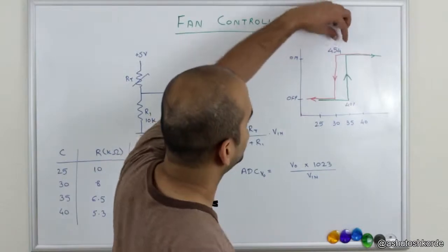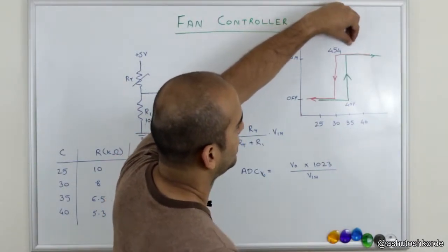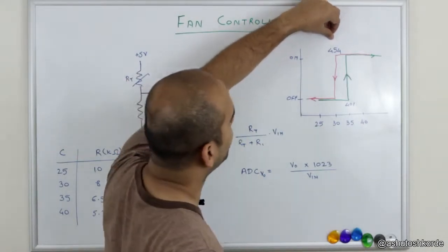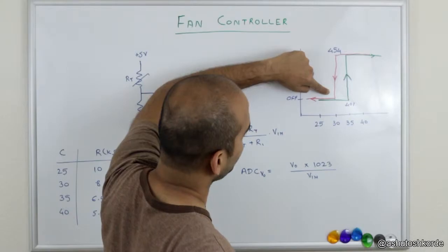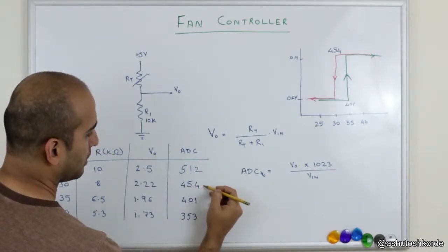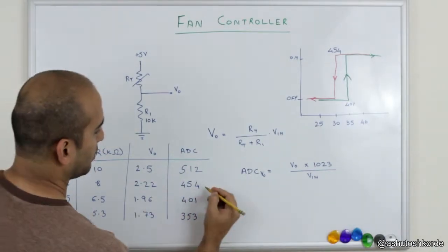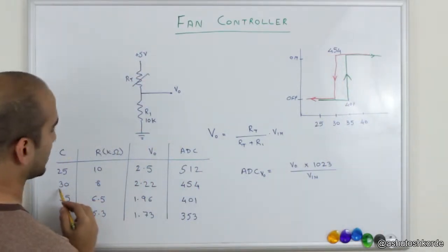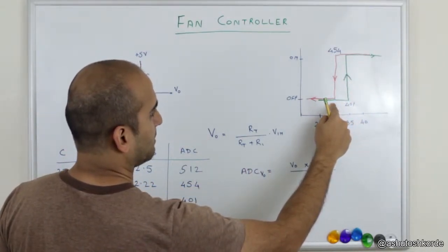What we do is we actually wait for some time, or to be exact 5 more degrees, for it to drop before we turn off the fans. That effectively means when the value reaches 454, which is 30 degrees, we turn off the fans. And then effectively this process will repeat.